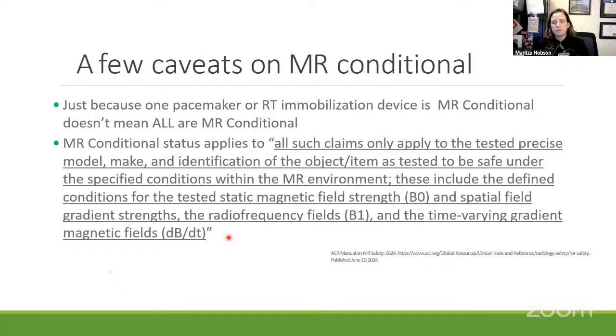So if a device was tested and determined MR conditional at 3 Tesla, that doesn't mean it is at 1.5 Tesla or 0.35 Tesla, which is one of the MR Linac vendors' field strengths. The gradient slew rate that they mention in the statement is also one that a lot of people forget to look at the specifications of your system for.